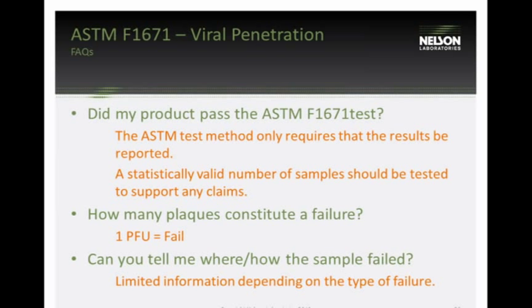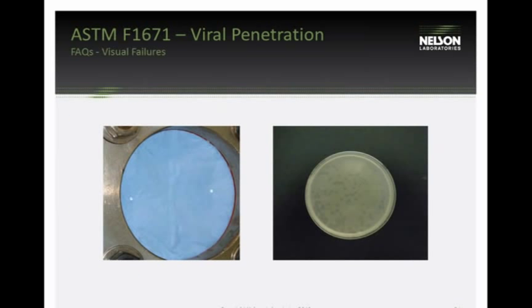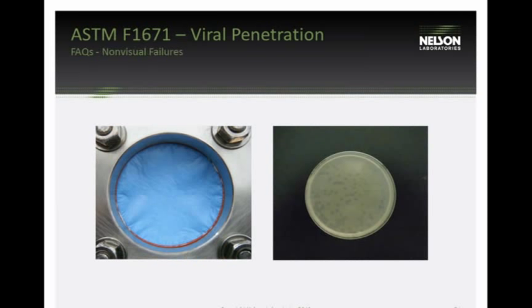Once a failure occurs, we can sometimes tell how or where the sample failed. For visual failures, we can identify whether it came from a seam, tie, or other location. For non-visual failures, there's nothing to indicate how or where the failure occurred — we can detect that virus got through microscopically, but not how. That's one limitation of the test: it tells us pass or fail but not much more.